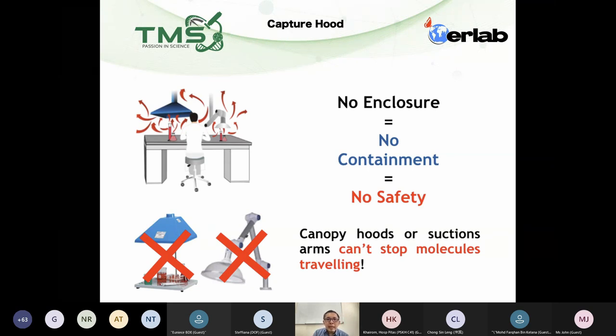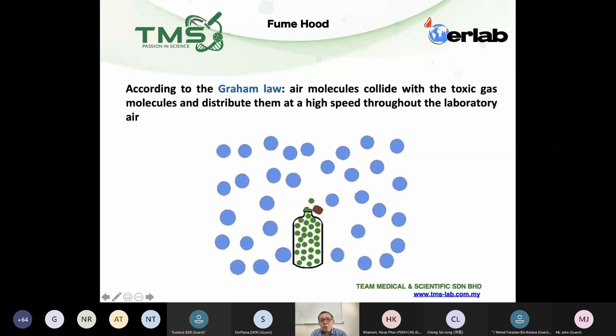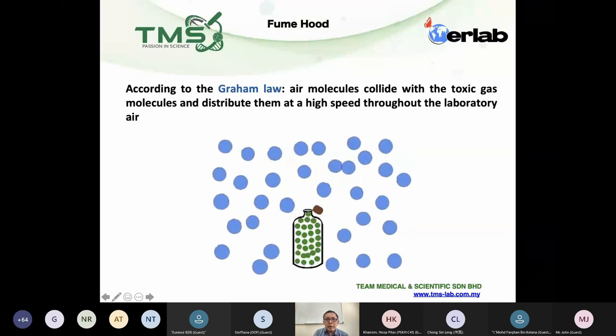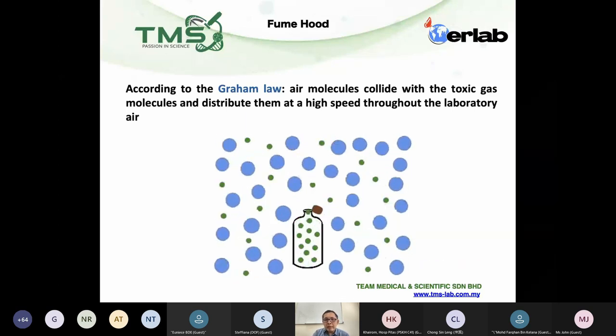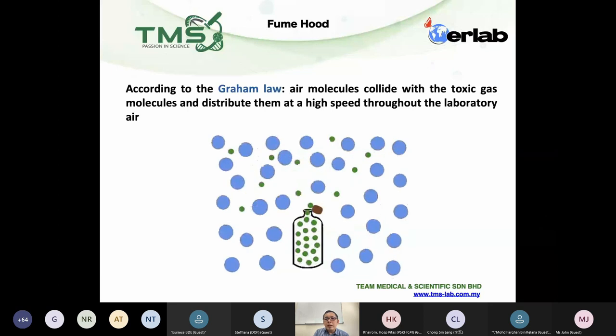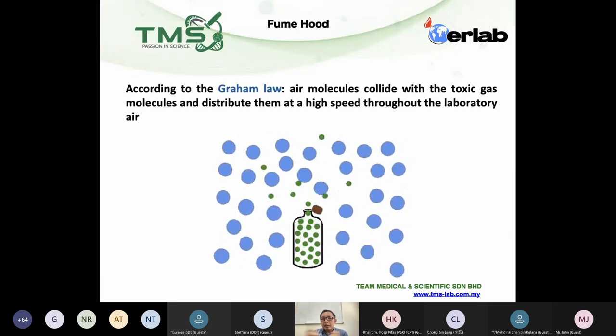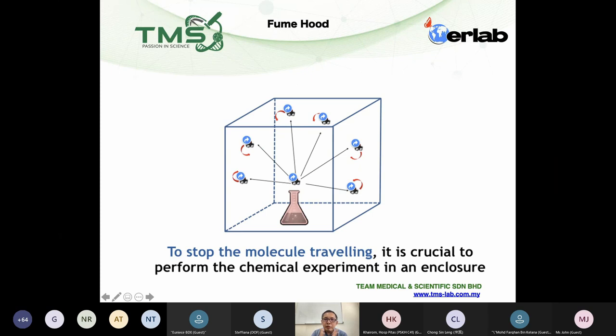When you open chemicals on the open bench and your suction arm is at the top, it can only withdraw maybe 50–60% of the fumes depending on the distance. The remaining will go back into the room or you will inhale it. There is a place where you use a canopy hood — especially for heated fumes, like furnace systems. But for liquid chemicals at room temperature, the suction arm is not efficient because of Graham's Law: chemical vapors spread in a fraction of a second once you open the bottle, before the suction arm can withdraw them.